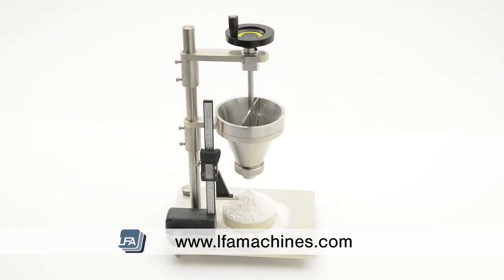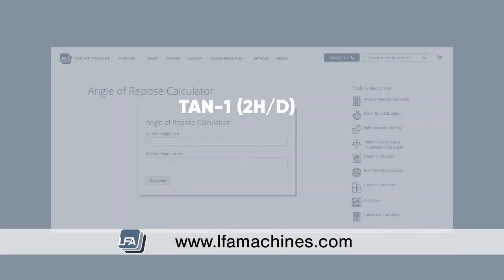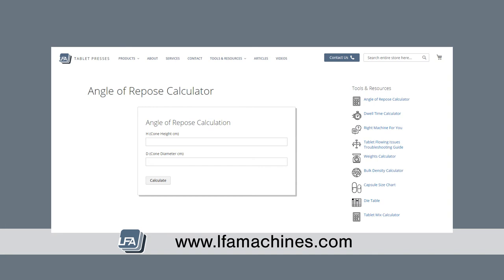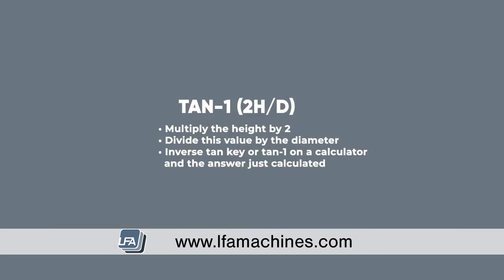The tangent of the angle of repose in degrees can be determined by reading off the height of the powder cone in millimeters from the digital display. Here is the calculation to determine the angle of repose — however, LFA also has a calculator on their website to do the math for you, linked below. The formula is: tan⁻¹(2h / d), where h is the height of the pile and d is the diameter.